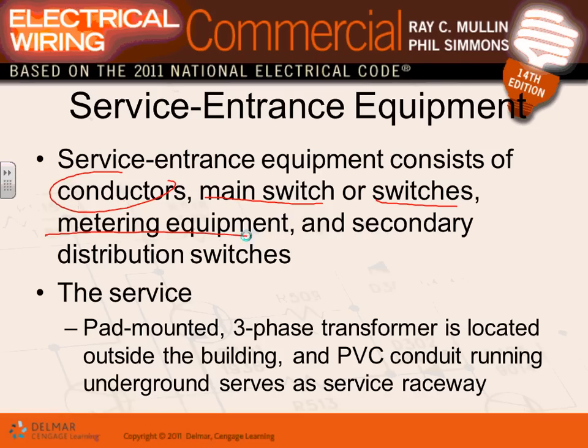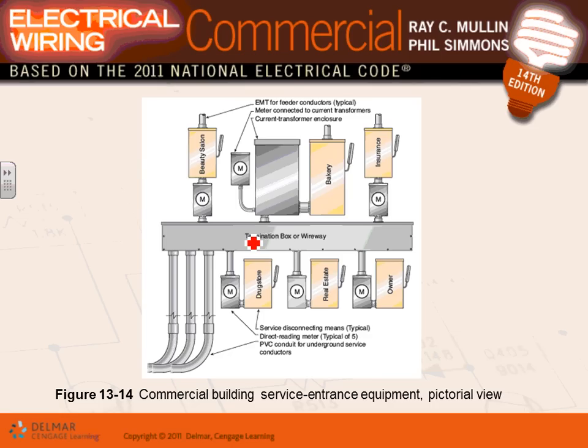conduit inside your building. So here's the building, the commercial project building. Can you see that we're paralleling three sets, bringing the cables here, and we're tapping these to feed different tenants. That's one way of bringing service conductors. You bring one service conductor to the building, and from that service conductor you tap it. Can you see that? That's if you have multiple tenants in the building.